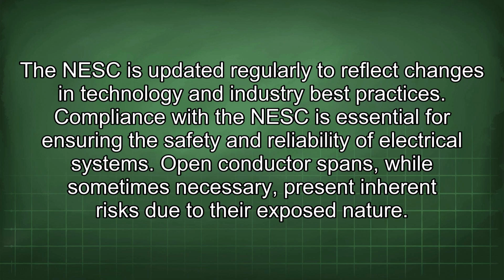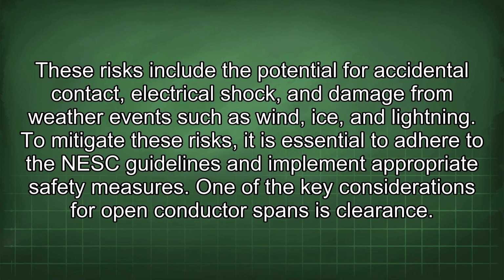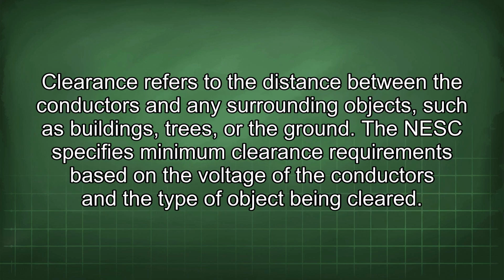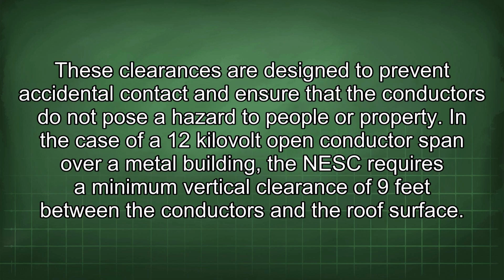Open conductor spans, while sometimes necessary, present inherent risks due to their exposed nature. These risks include the potential for accidental contact, electrical shock, and damage from weather events such as wind, ice, and lightning. To mitigate these risks, it is essential to adhere to the NESC guidelines and implement appropriate safety measures. One of the key considerations for open conductor spans is clearance. Clearance refers to the distance between the conductors and any surrounding objects, such as buildings, trees, or the ground. The NESC specifies minimum clearance requirements based on the voltage of the conductors and the type of object being cleared.